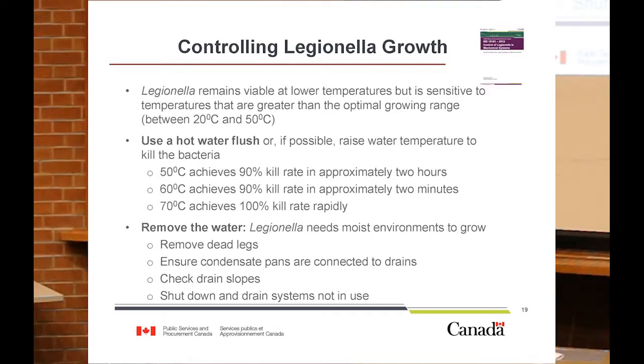The other way to remove risks associated with Legionella growth is to actually remove the water. Legionella needs a moist environment to grow. So if we can remove those dead legs where they're present, ensure that our drain pans are draining properly, and also shut down systems and drain them if they're not in use. So if you have a cooling tower that is cycling on and off and you only have it there for backup, don't pre-charge it ready to go. You need to do your startup when you need it, and then if you're not using that tower, make sure that it is drained.